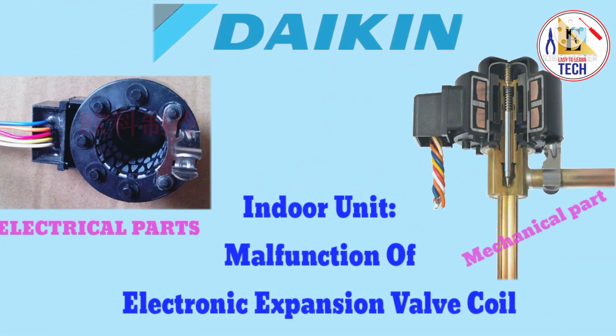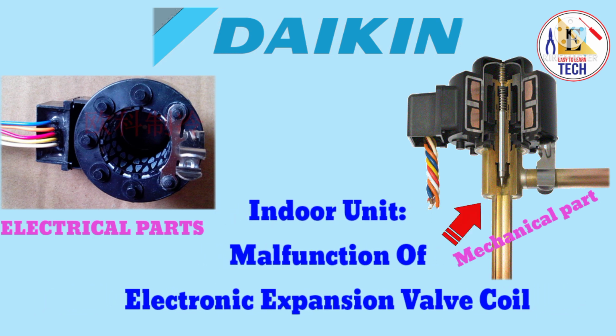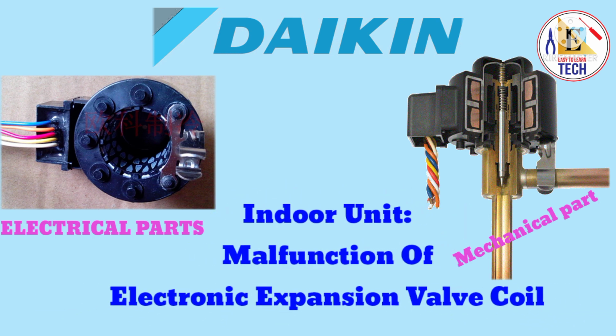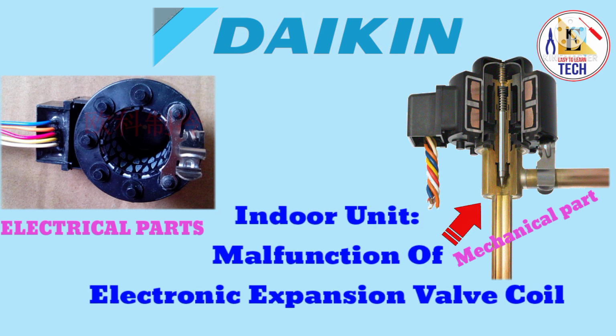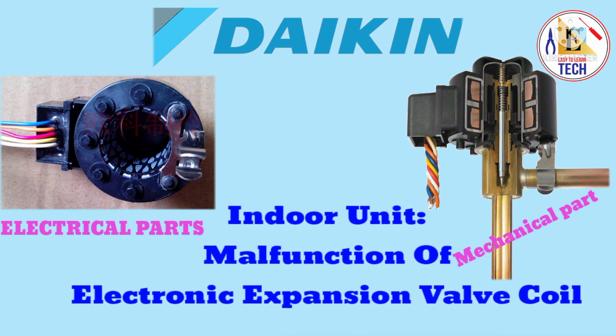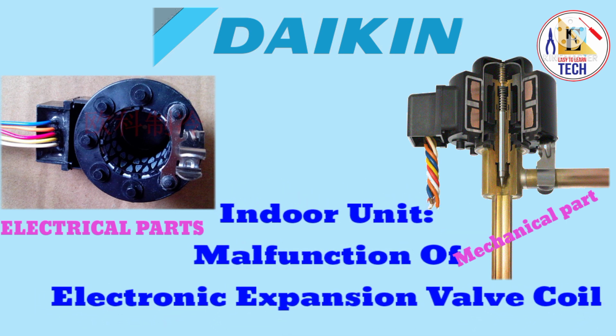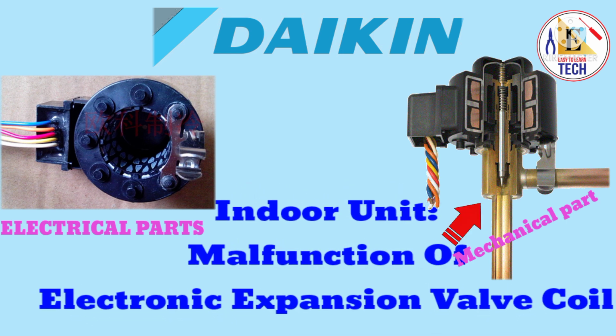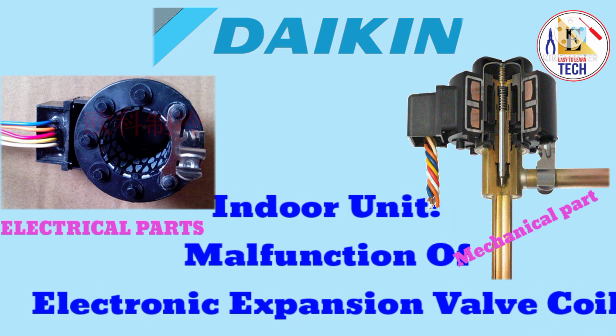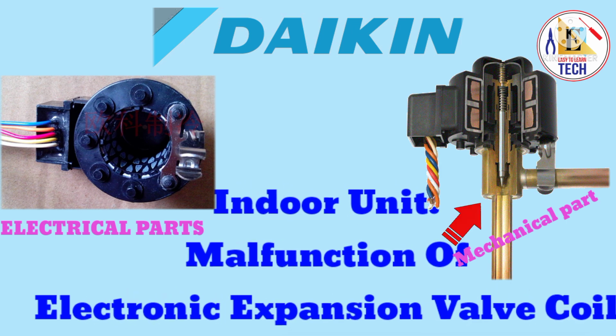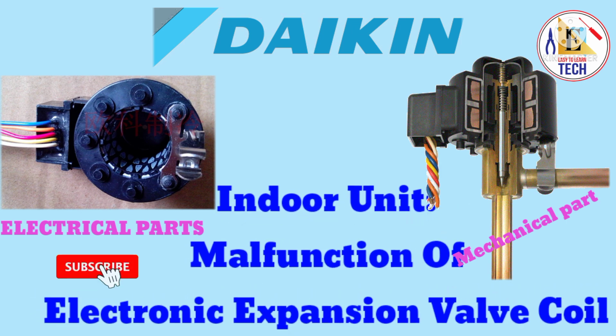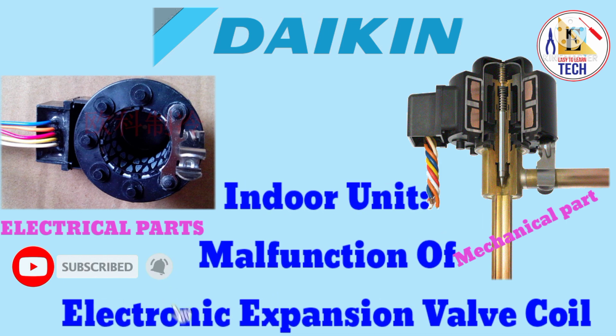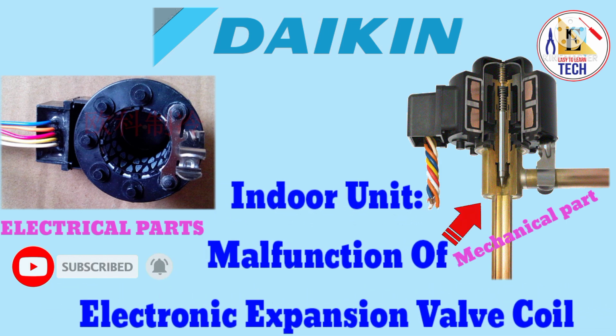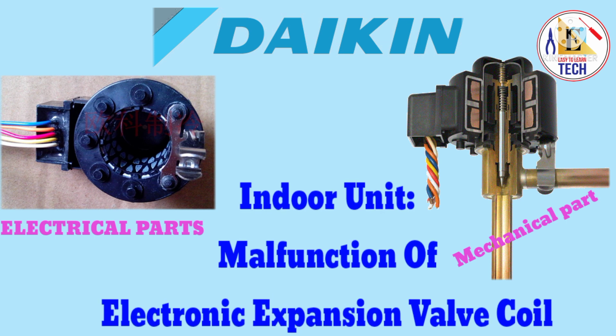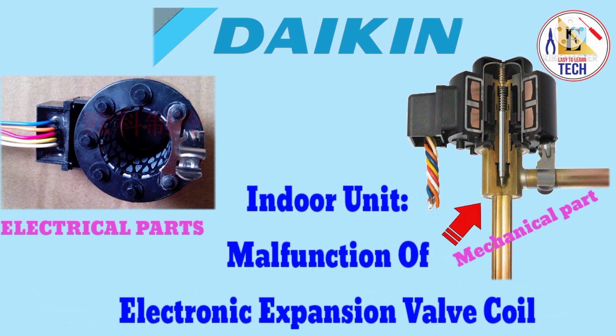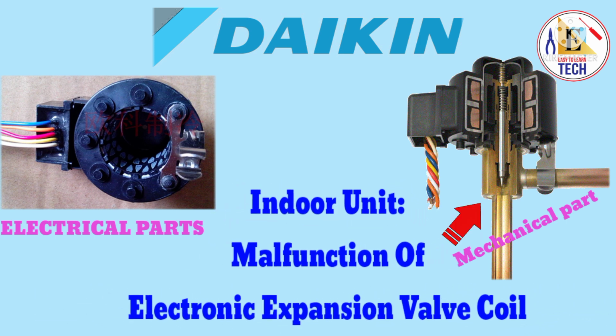Let's see what are the causes for the error A9. A9 means our electronic expansion valve is faulty. At that time you will see the error A9. This expansion valve is divided into two parts. One is electronics, one is mechanical part. If our electronic part is failure, at that time also you will get the error A9. Or our mechanical part, if it is showing some disbalance or is not operating properly, at that time also you will get the error A9. A9 means our electrical part or mechanical part failure.